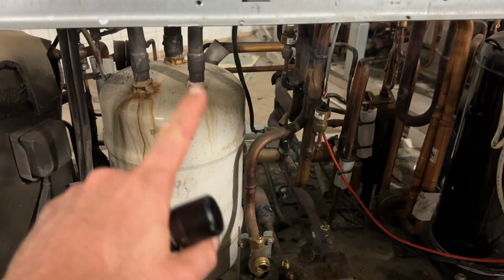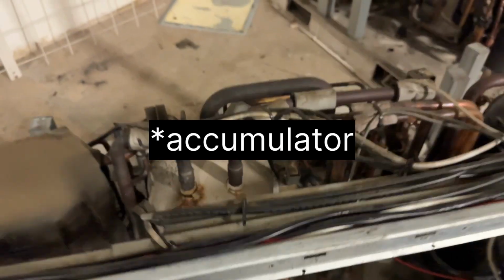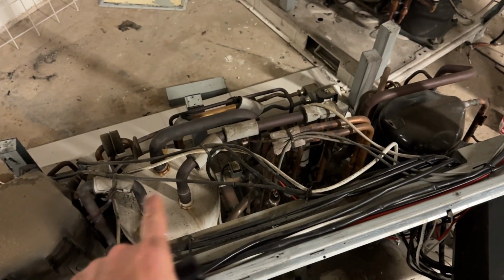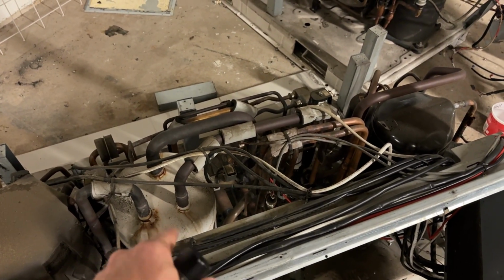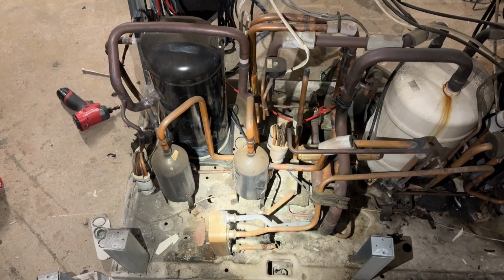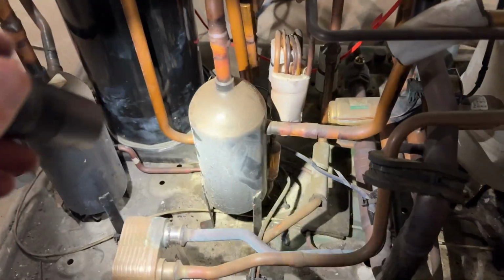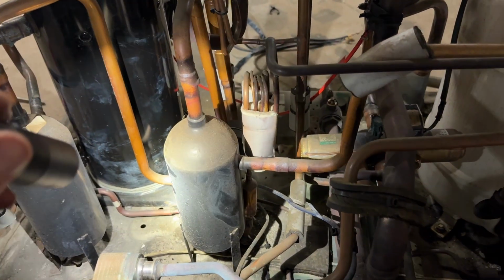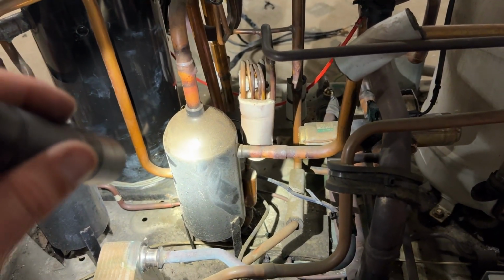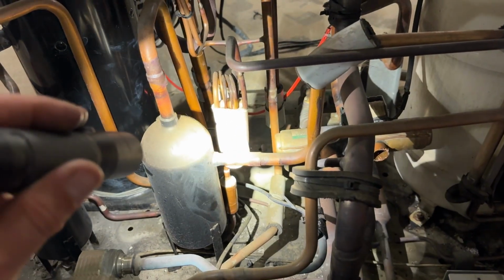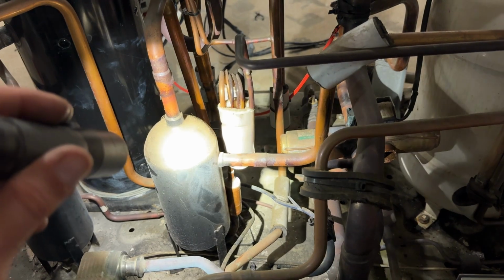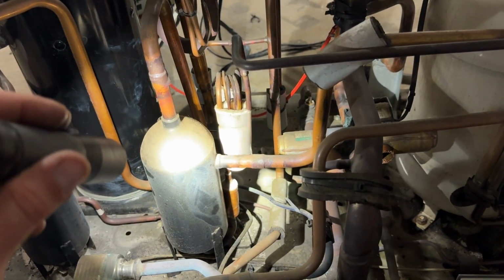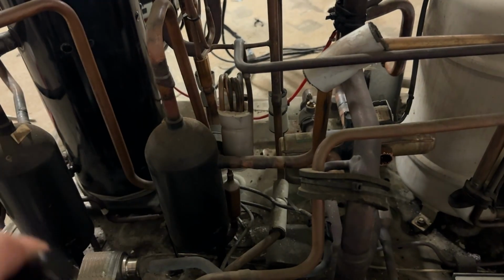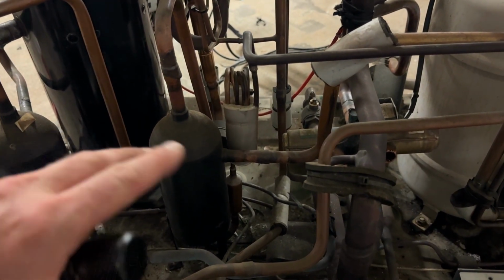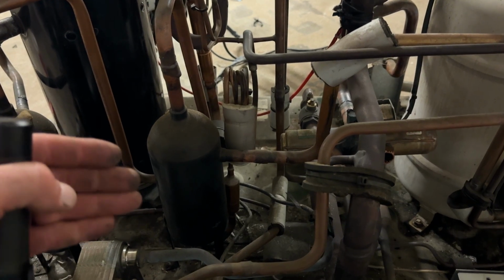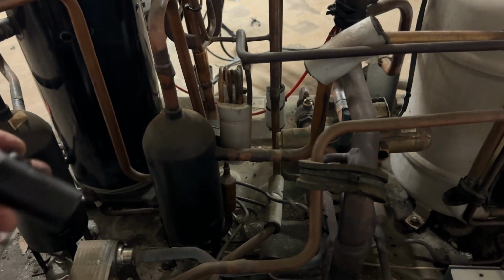Now, you've got a receiver over here that's used for both compressors, so they don't care where the refrigerant's coming from, just as long as they have it. This right here is an oil separator, and oil return can be a huge issue with VRF units. They have more components than traditional units to deal with oil return, because part of the problem is the change in velocities you're getting, like when 3 units cut on instead of all 25 units.